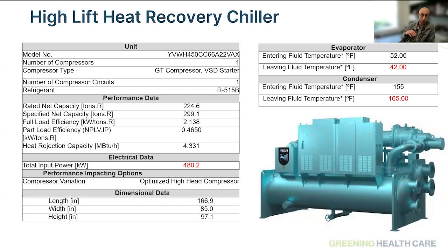And then during the summer, when you need peak cooling, you can run your cooling only centrifugals, or whatever your main chiller plant operates on, with that 0.5 kilowatts per ton that you want to see. Thanks, Robert. We're looking forward to the data coming out of this project, because we have a lot of interest in this, and a lot of other facilities have interest in the applications of these heat recovery or high lift heat recovery chillers in these existing facilities.